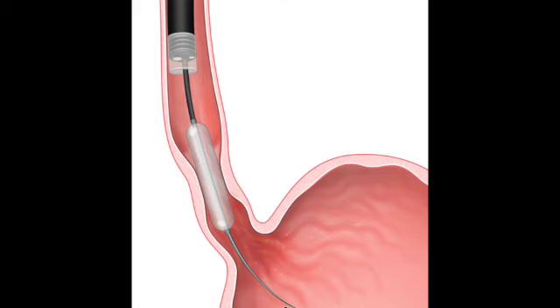But why is the distinction between air and water so critical here? It's a great question. I mean, if the goal is just to inflate a balloon, why go through all the trouble of measuring out exact cubic centimeters of fluid? It all comes down to compressibility. Okay. Air is a gas, which means it is highly compressible. So if you use pneumatic pressure, air pressure inside a stricture, the air acts like a spring. I see. When the balloon meets the heavy resistance of the narrowed tissue, the air inside simply compresses before it expands the balloon. So it builds up potential energy.